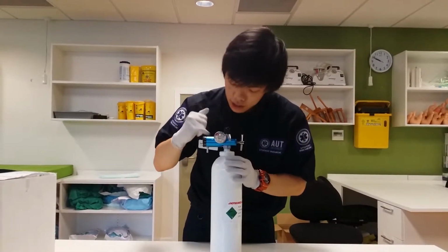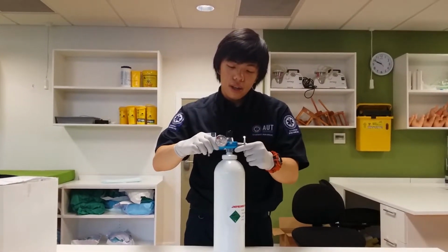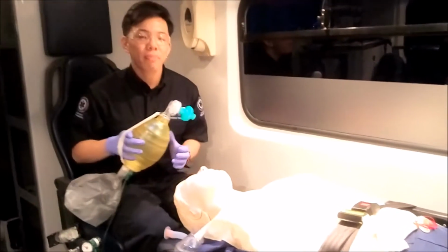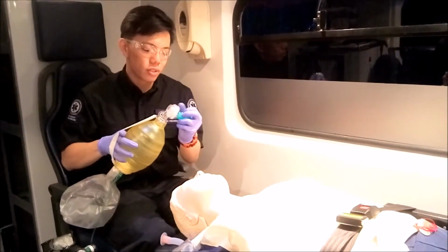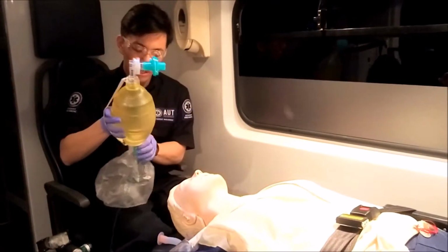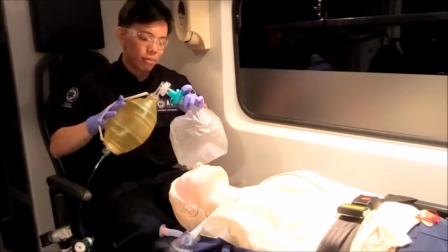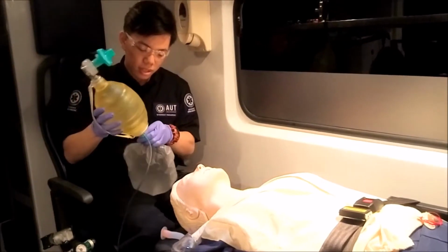So now once it's reached 0, you just loosen this lever here, and it's all done. Before using the bag valve mask, ensure that there are no leaks in the BVM itself. So I'm just going to occlude it like so, and squeeze on it so there's no leaks in it. It's good. And I'll be checking whether the reservoir bag is able to fill adequately and that there are no leaks. So yep, that's good.